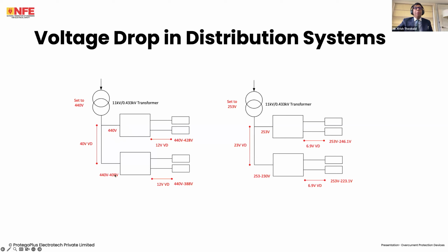So I am designing for the furthest point, but I'm ensuring that the tapping is not set such that the voltage available at the closest point to the transformer exceeds the maximum voltage allowable. Normally, like I said, we think about the lowest voltage because it's voltage drop, but because we are designing for, say, a very long run, we need to ensure that the closest point of utilization does not have a voltage exceeding the maximum, taking into account the tolerance.